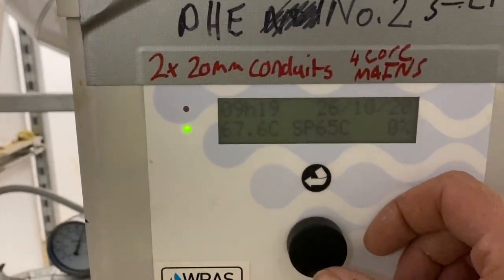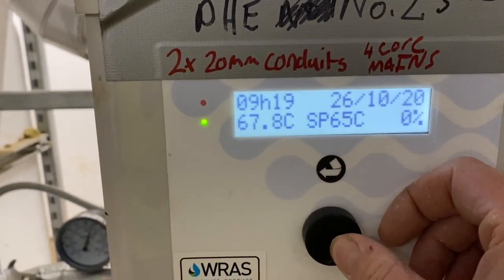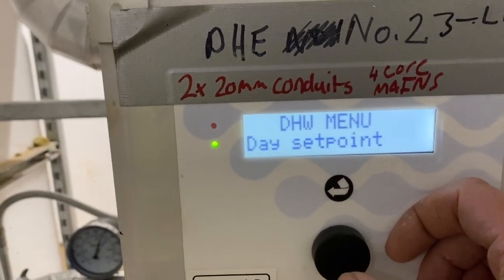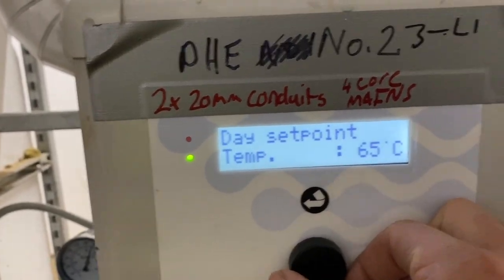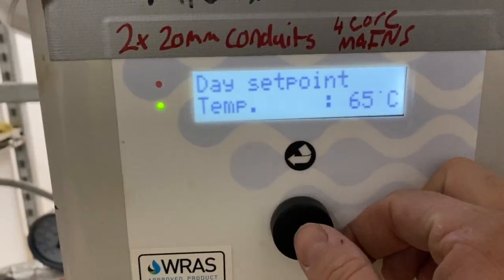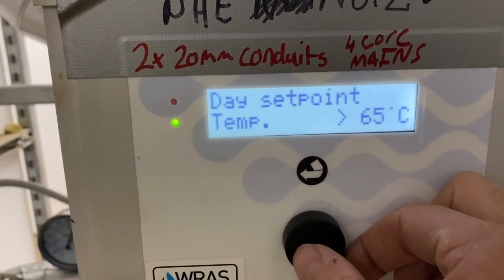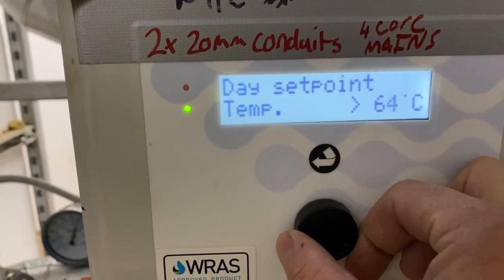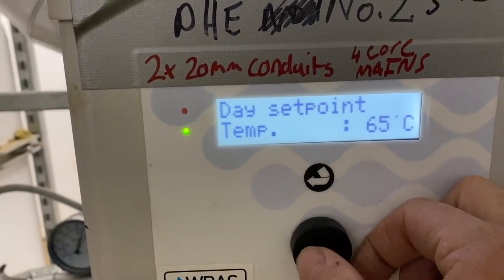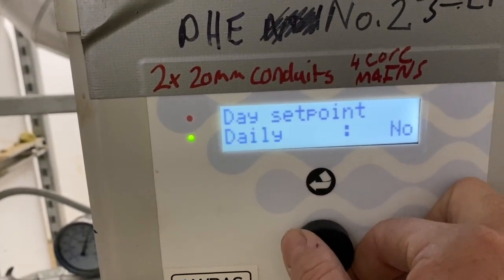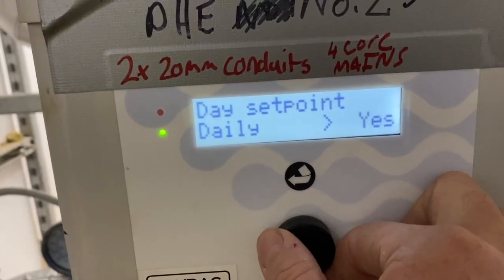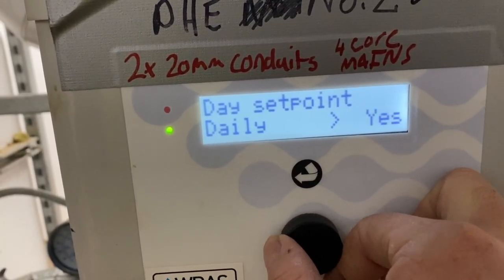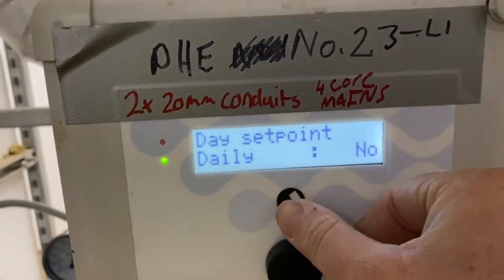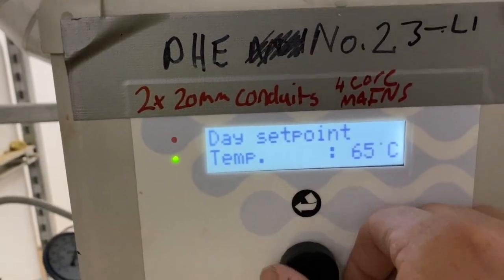So we have the controller and the Propak. This needs to be pressed the center button until it says let go, and it'll give us various options such as the temperature set points, etc. Some parameters need to be set through admin mode, which it's not showing here, but if you take it all the way to admin mode, select yes, and then come back, you can change our daily set points.